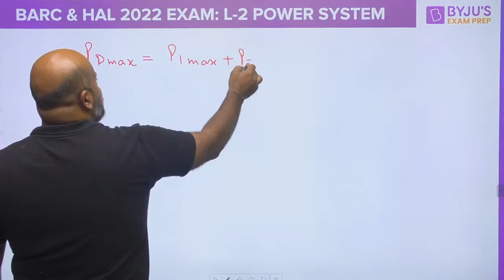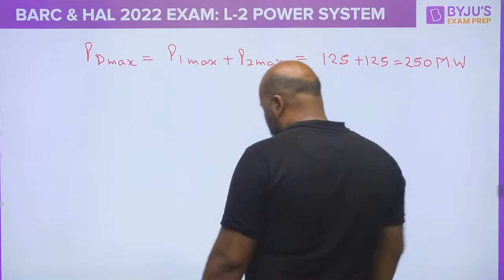So what you will do is go to the minimum and maximum generation limits, and say the maximum generation limit for both units is 125. So we will use P1 max plus P2 max, and that will be the maximum power which can be supplied, that is 125 plus 125, which is 250 megawatts.